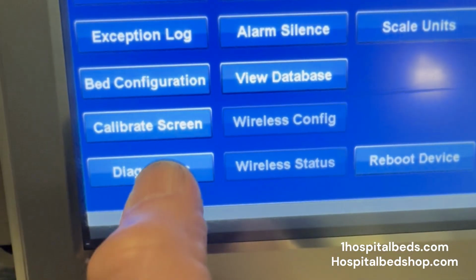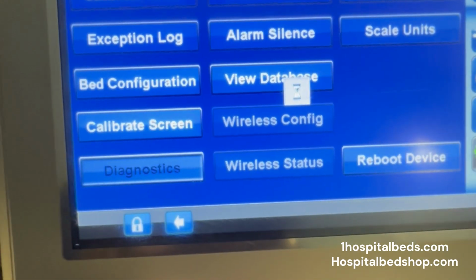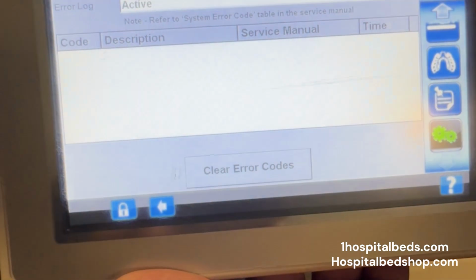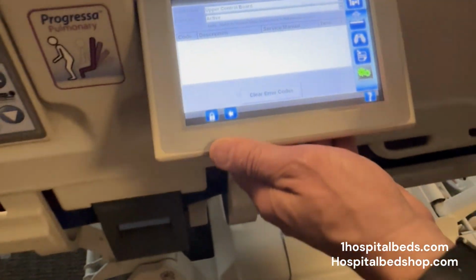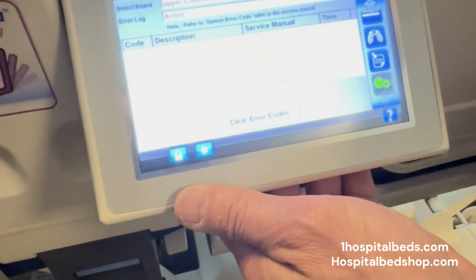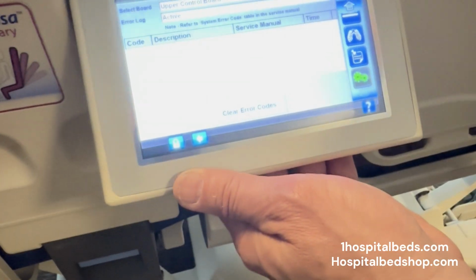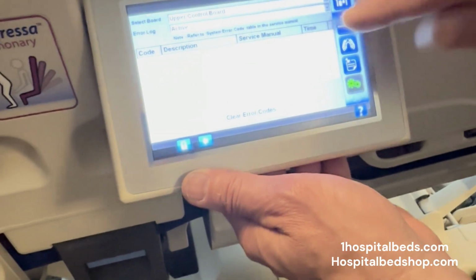and check for any error codes under the diagnostics tab. This will tell us what's going on with the entire bed. It does a full accounting of the air surface, the compressor, the blower, the electrical systems on the bed, and it will tell us up here.